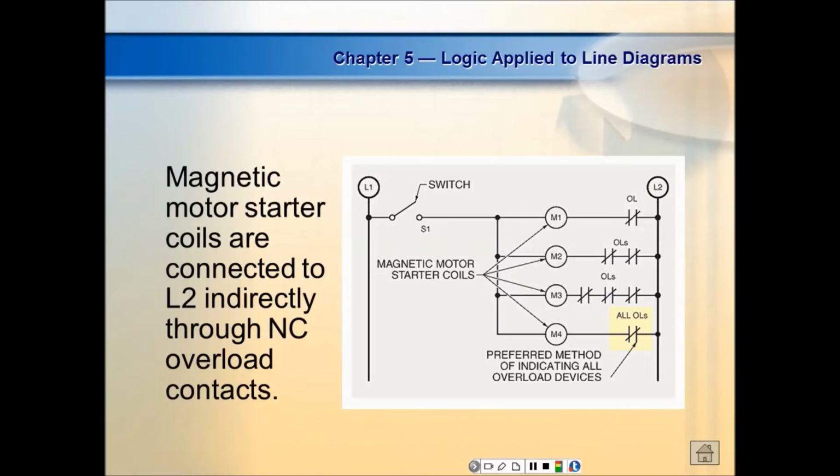Yeah, what we're trying to do is move power from everything over here. Okay, understand? So if I come up here and open up that switch, and then I get between hot and here, then it's still going to be literally hot, right? Well, not hot. It's still going to have voltage through this thing up here. If we open up here, then if I get between here and there, it's not going to cause any problem because it's open. So the overload is the only thing that's allowed to go on the L2 side of the load.